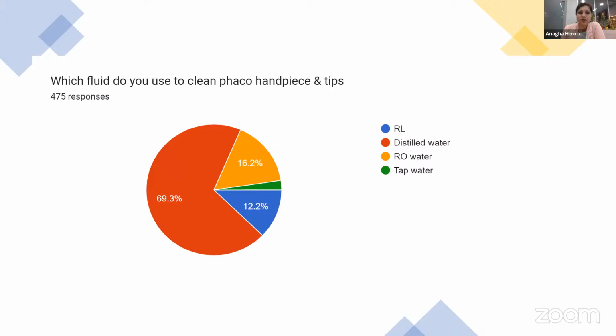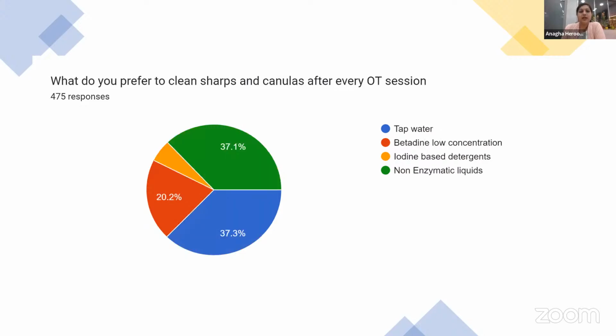Regarding cleaning of the phaco handpiece and tips, although 69.3% are using distilled water and 16.2% RO water, there are still some people who are using tap water, and RL is also being used in 12.2%. So it's very important to use, as we had discussed, RO water or distilled water only.